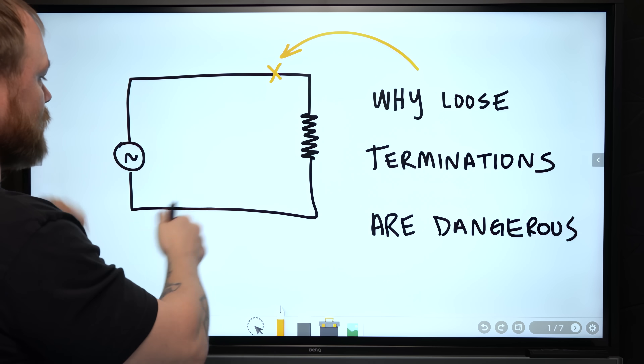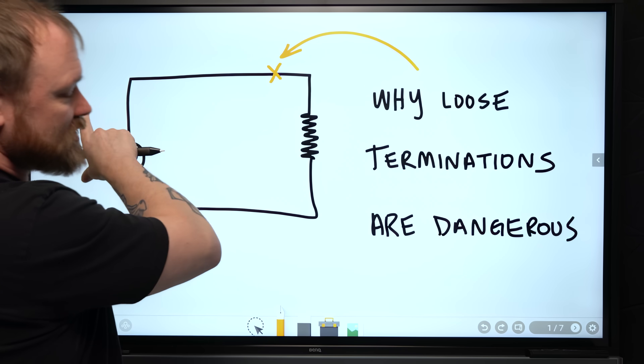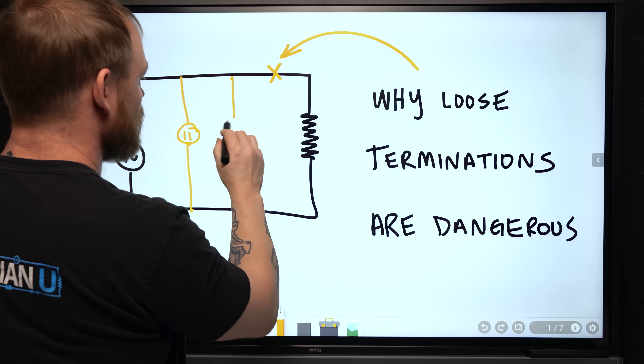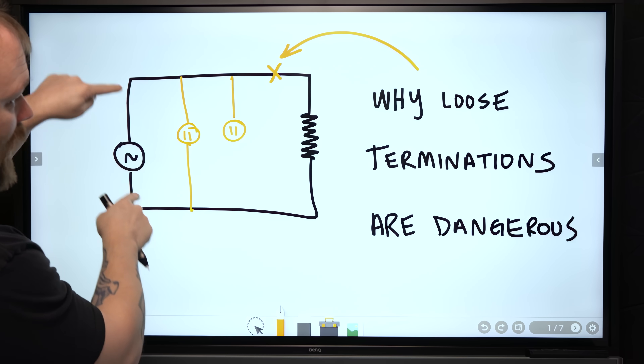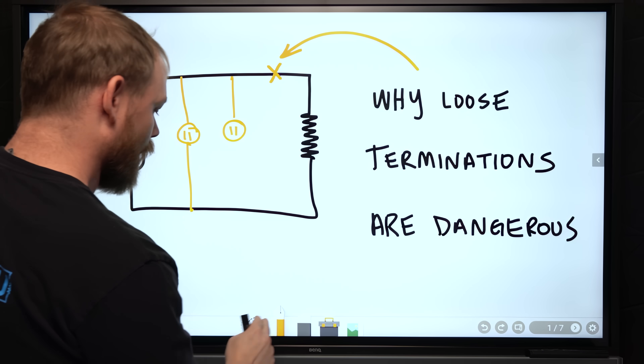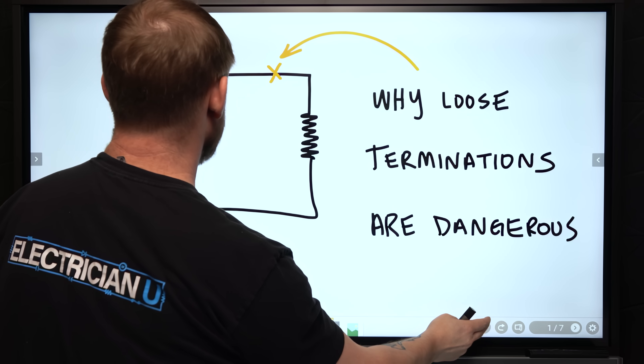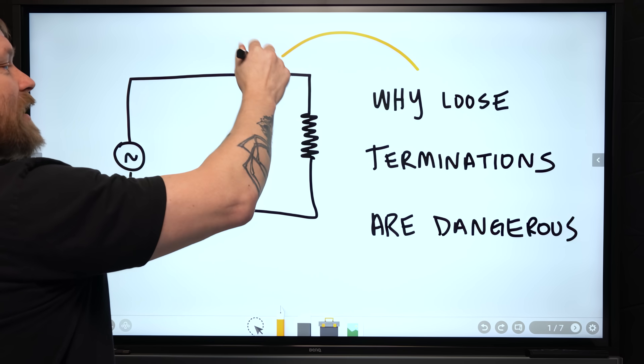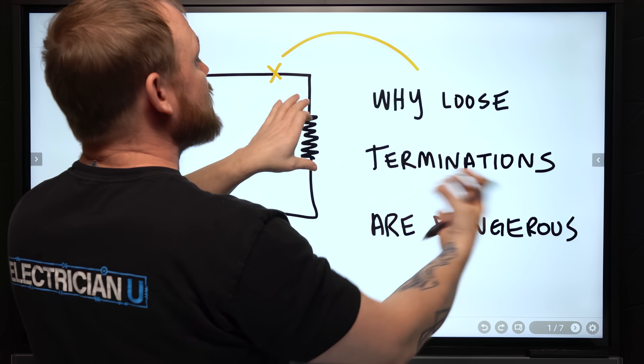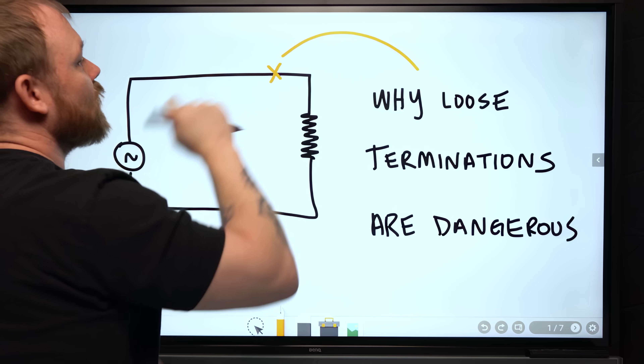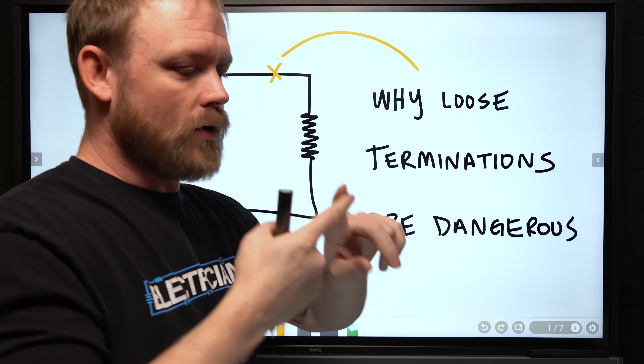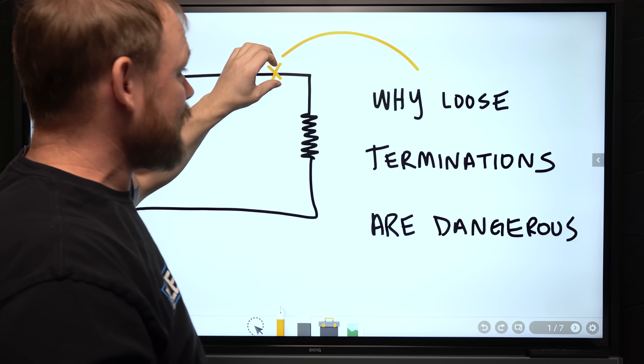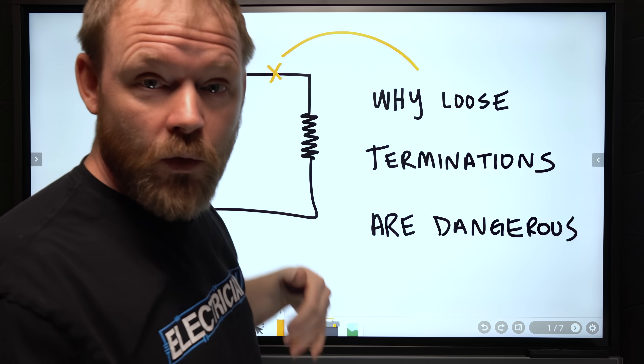In a house circuit we have an AC power supply. In houses, we have parallel loads — receptacles all run in parallel. When we run a branch circuit, we have a breaker, a hot and a neutral, hitting each receptacle. In our case, we just have a single load in series with the rest of the circuit. If there's a joint somewhere — two blacks start to come apart or a neutral termination starts to come apart — we're adding a resistance in series with our load.